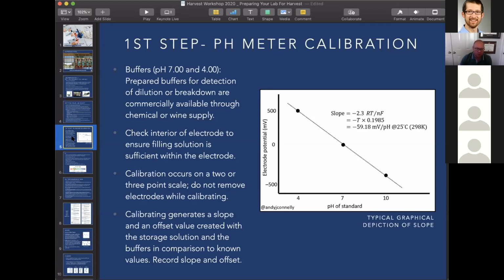What many people will say, all of the different pH manufacturers, is a slope between 85 and 105%. So you want to have your slope between there. At the Surrey Winery, we typically like to be around a 90 to a 95% range. This is specifically referring to the accuracy of your pH reading, and of course the condition of the buffers. And then in addition to that, we also look at the millivolt offset. So you should be plus or minus 30 millivolts. That's the recommendation for that measurement as well. So you should look at both the slope and the offset.